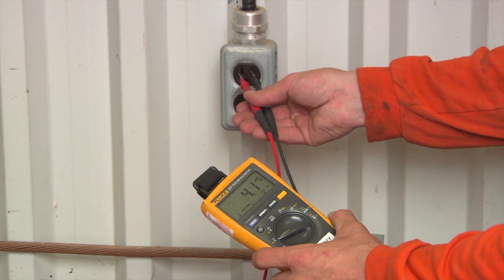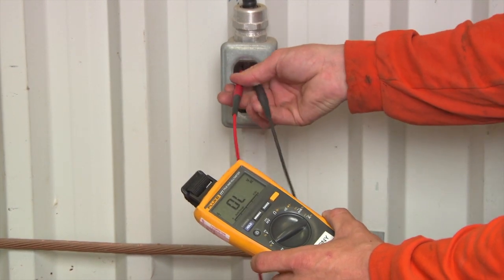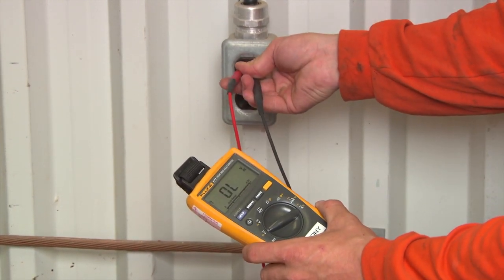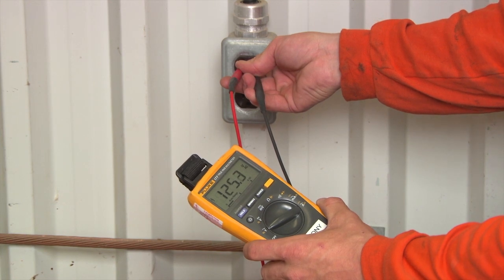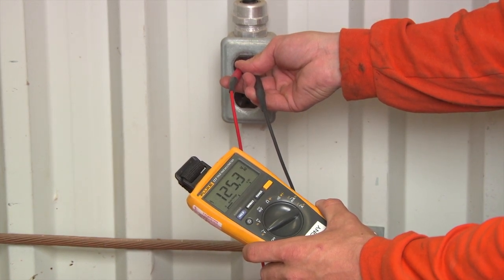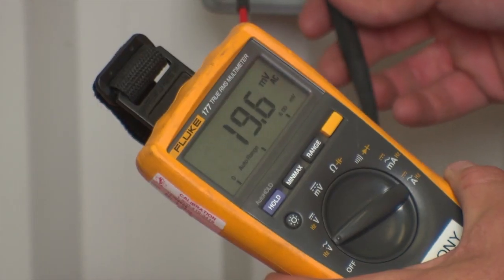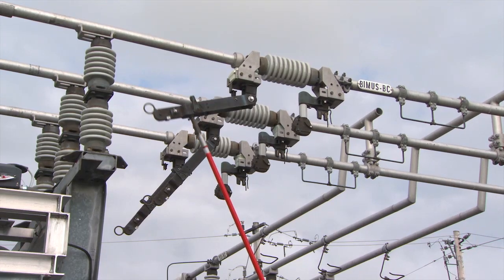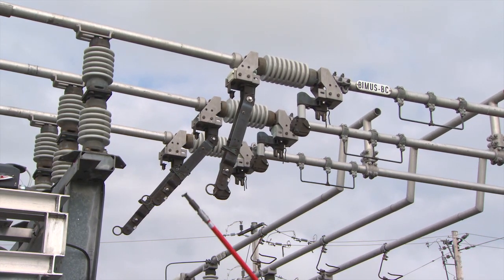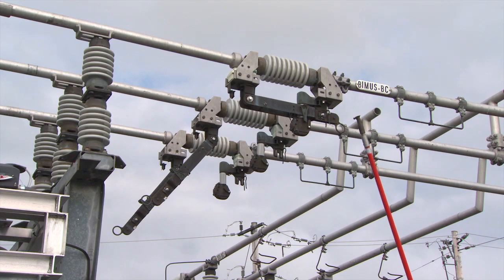Check and adjust the DS voltage to match the MUS. The DS voltage should be approximately 3 to 5% higher than the MUS voltage. Close the DS low voltage switch. The MUS and DS are now in parallel.